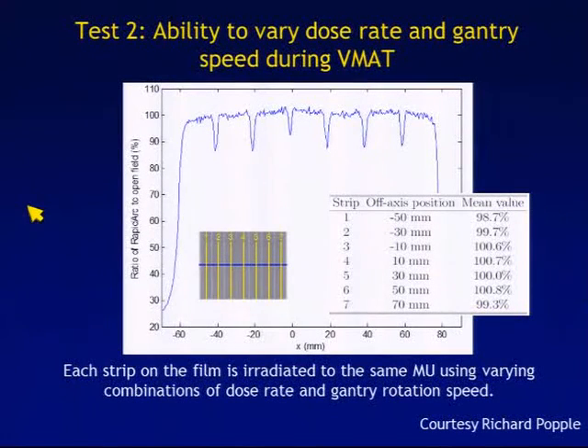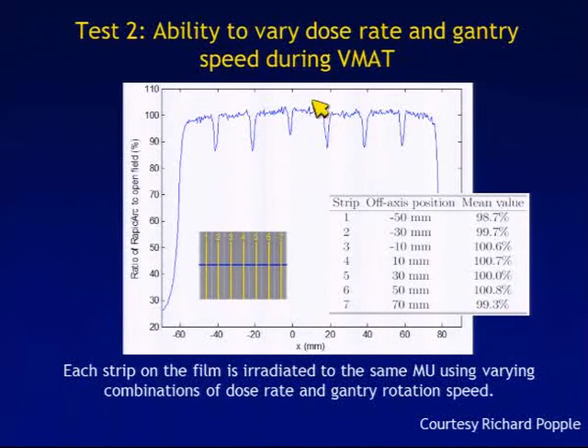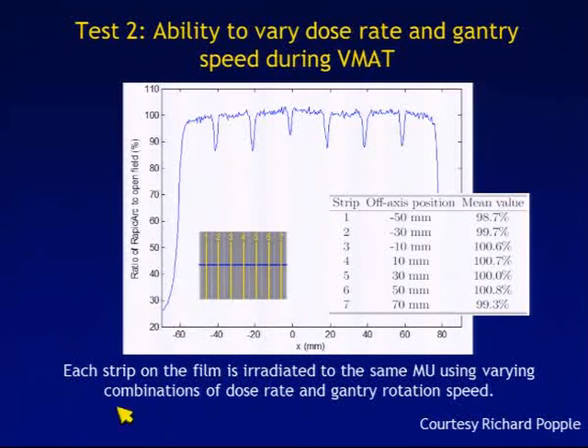The second test is testing the ability to vary the dose rate and gantry speed during VMAT. On the film, a series of strips are delivered, with each strip irradiated to the same monitor units using varying combinations of dose rate and gantry rotation speed. The results show strong uniformity between the various strips.